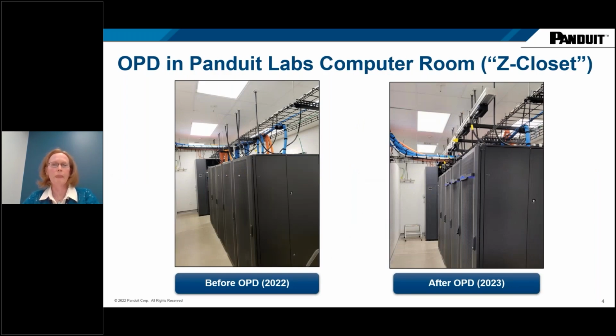Here we're showing some pictures from our own internal labs. We've recently installed OPD in one of our computer rooms—we call it our Z closet. You can see before we had whips coming from above the cabinets up to the ceiling, versus now with the overhead power distribution, we have this nice clean product that runs overhead, and the whips come out of the cabinets and plug right in. We've suspended this from the threaded rod that comes from the ceiling, and it's sitting on some unistrut.